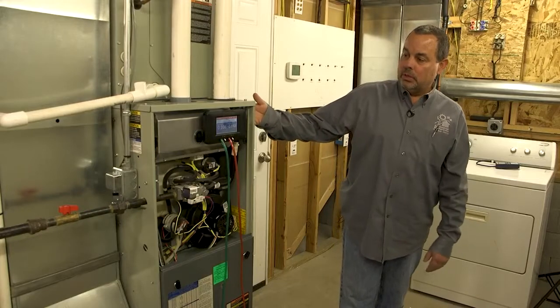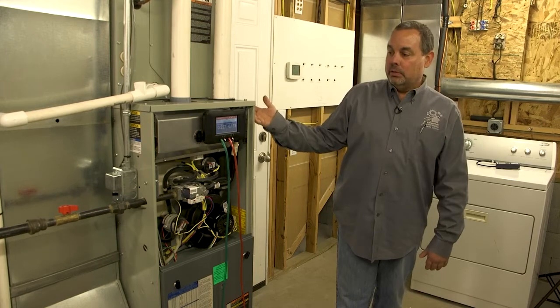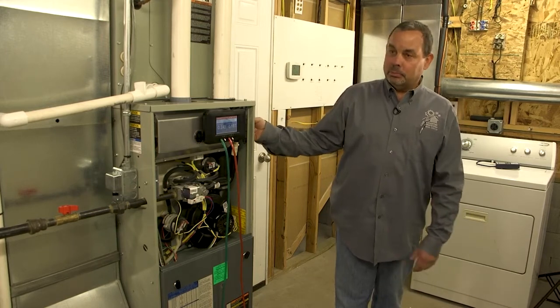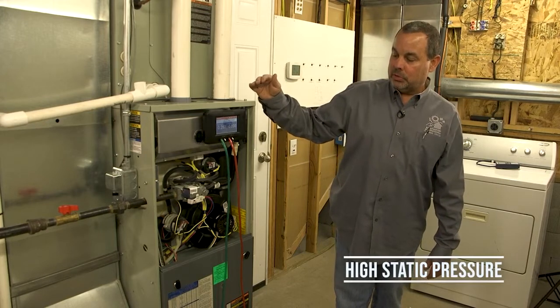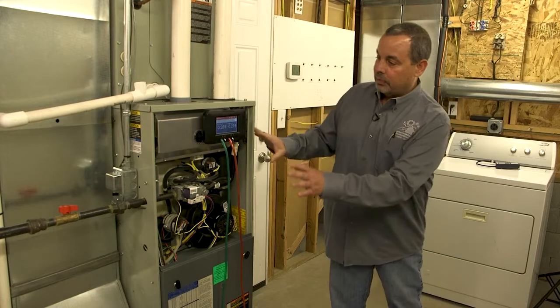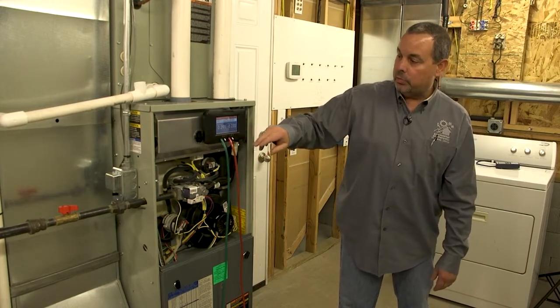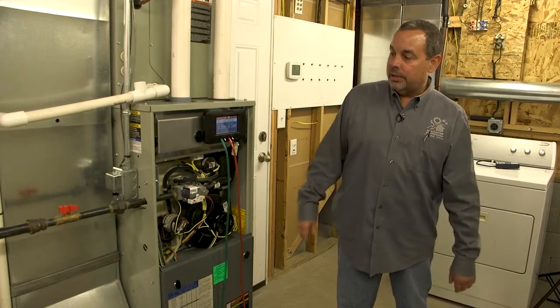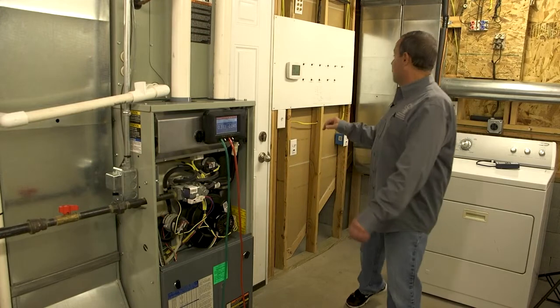Show us more. Okay. Your heating and cooling system creates pressure in the ductwork, and the higher that pressure, the more it becomes a problem. We call it high static pressure, and if you get extremely high static pressure on a system, it can start to cause issues with efficiency and airflow. So right now I've got the system running. We've got our measurements for static pressure here, and what I'm going to do is simply simulate a clogged up filter, and we're going to watch that static pressure start to rise up.